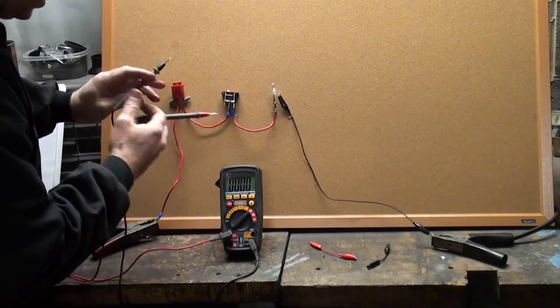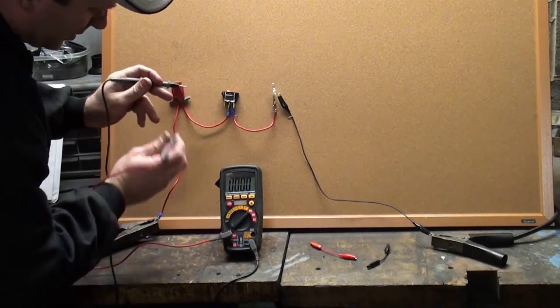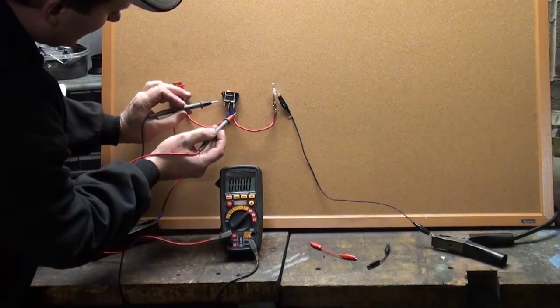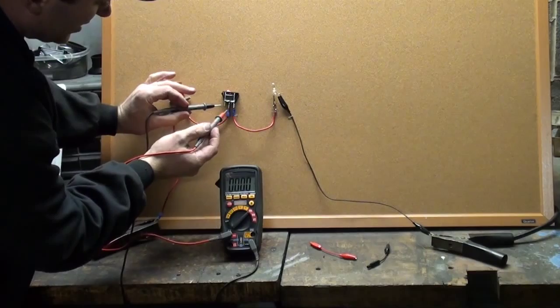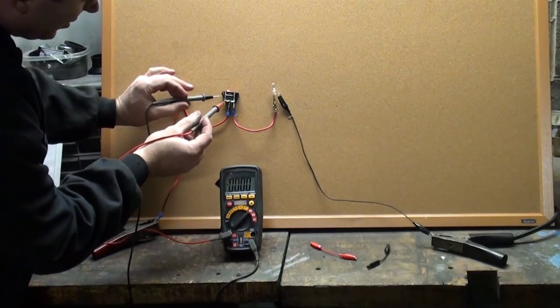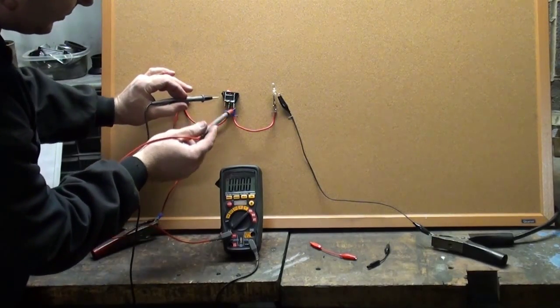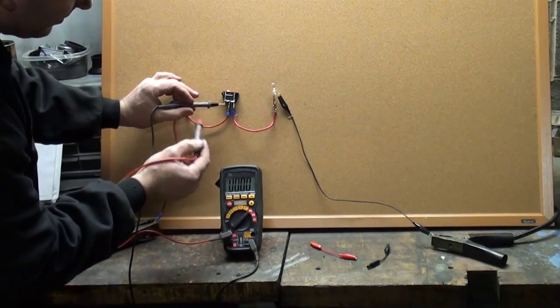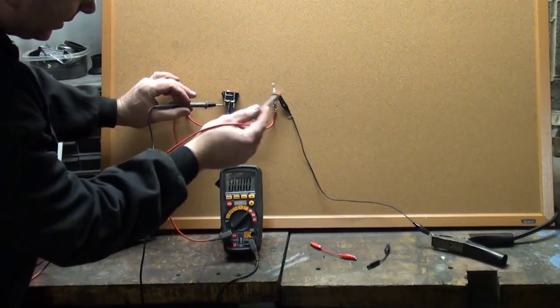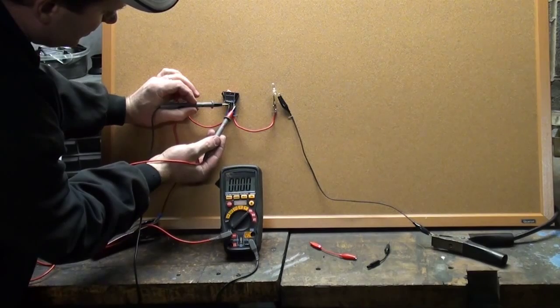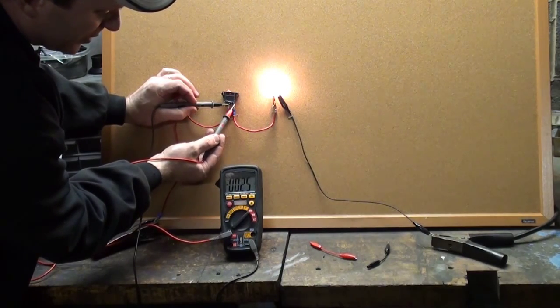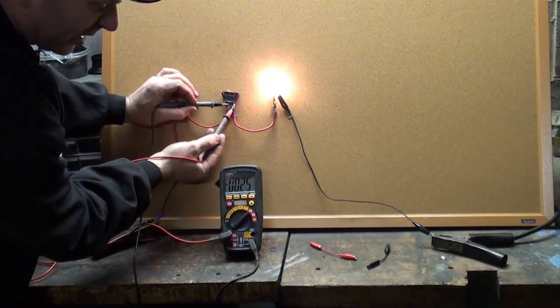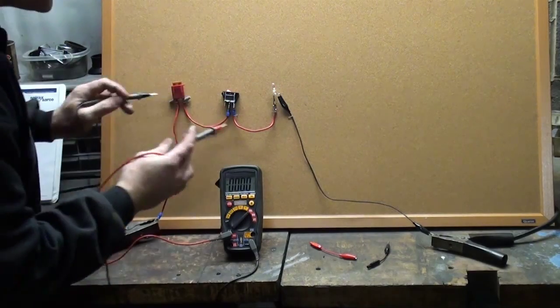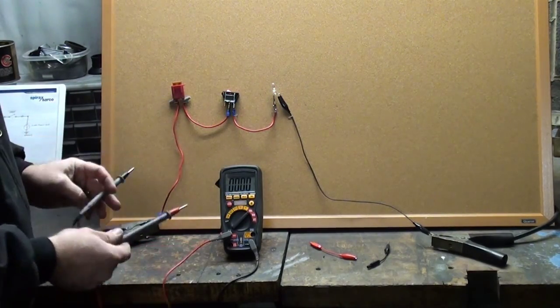So I got it all set up for amps, this is going to bypass the switch. Since the switch is open, instead of going through the contacts, it's going to go through my meter and complete the circuit. 0.25 - that's another spot you can take an amp reading. So as long as you can find an open in the circuit, you can check your amps.